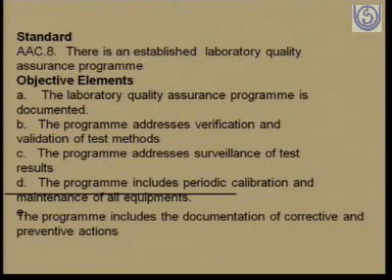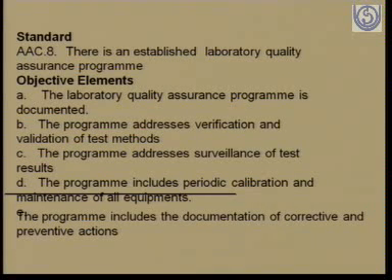That means there has to be continuous surveillance by all the heads of the departments of microbiology, pathology, and various sections. A sample should be taken out and surveillance has to be carried out. Periodic calibration and maintenance of all equipment is also very important, because nowadays it is totally automated laboratories, and this equipment will give you accurate results. If it is not properly calibrated, then there is likelihood that the results will go in different directions.